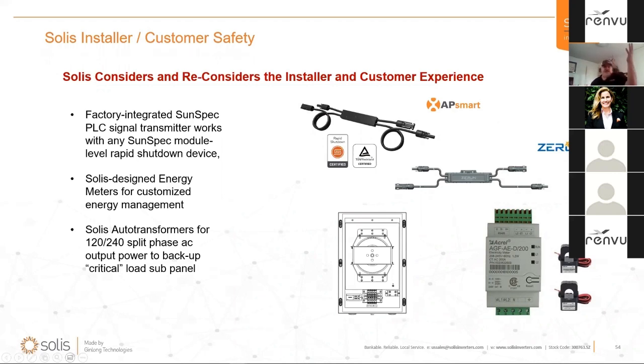And so what parts do you need? Well, the PV array, and you might need rapid shutdown with that, depending on which jurisdiction you're in. You might be able to get away with string level rapid shutdown, or even no rapid shutdown at all if you're setting up this battery with a larger HV battery and maybe a couple of other inverters. You may be able to get a pretty good outdoor type of system where you're ground mounting the PV array. But in most cases, especially residential rooftops, you're going to need some sort of rapid shutdown. And if you're under 2017 code or above, you're going to need to install these rapid shutdown receivers up on the roof. The transmitter, don't worry about it.